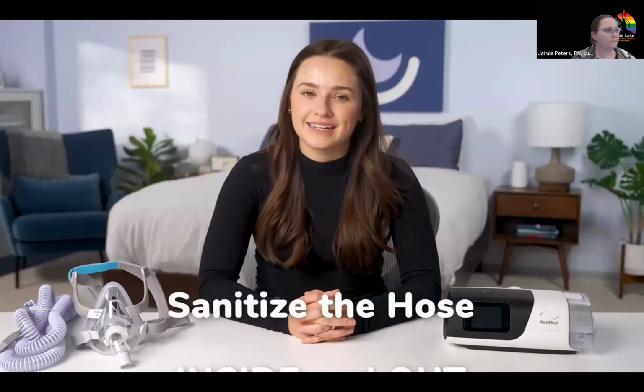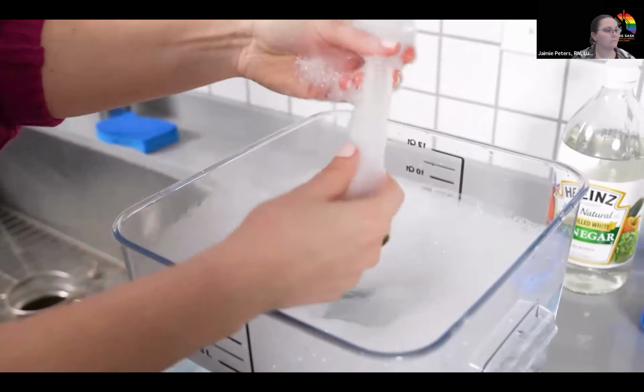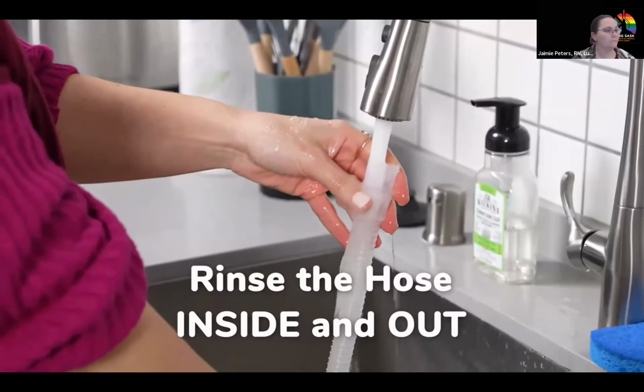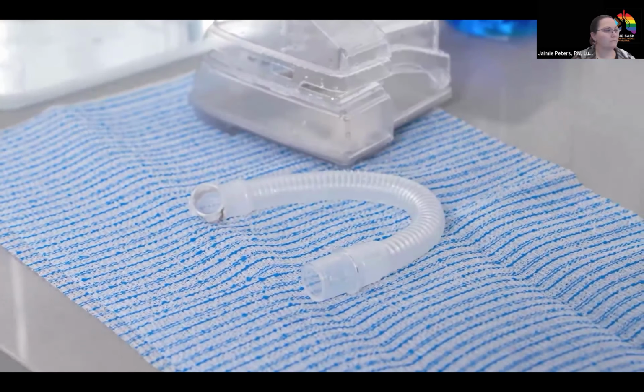This is why you should fully submerge these components in a clean tub or bucket with a mix of warm drinking water and mild soap. Soak these for a few minutes, remove the hose and tubing from the tub, and rinse it inside and out. Make sure to rinse until all the soap suds and the residue is gone. And then place the hose and tubing on a clean, smooth towel for air drying. As with the humidifier tank, make sure the hose and tubing do not air dry in direct sunlight.